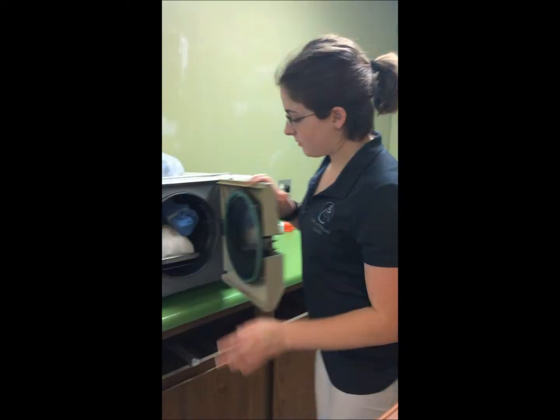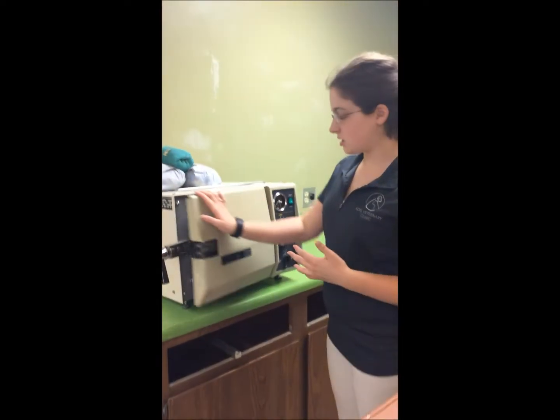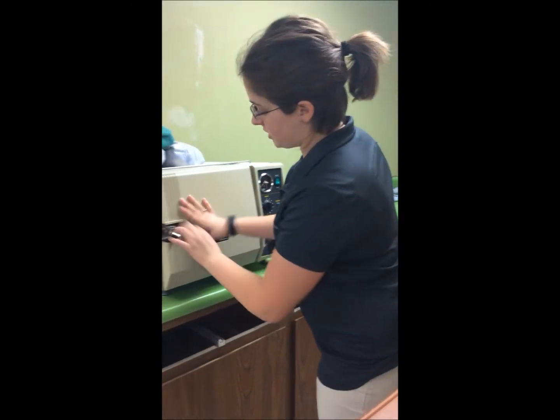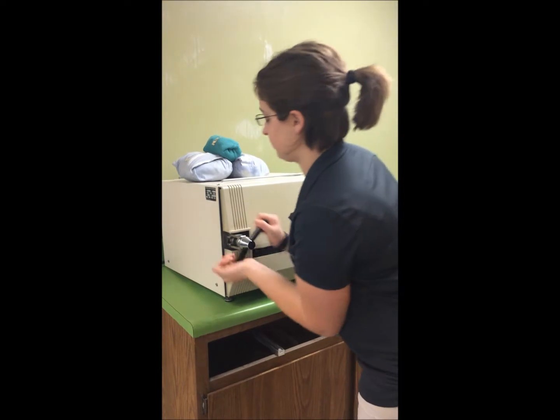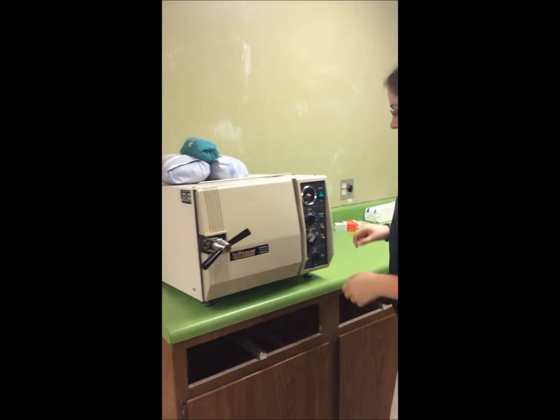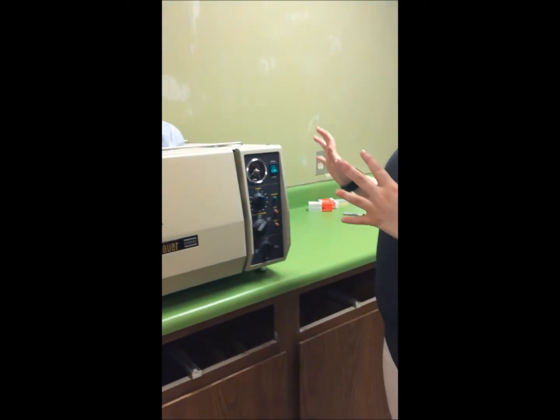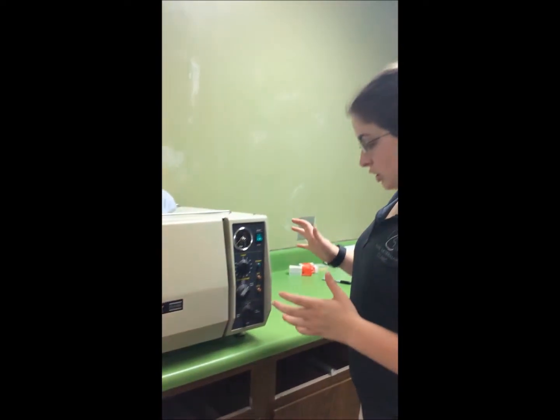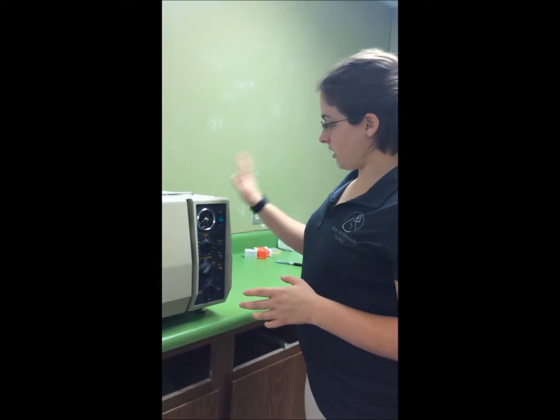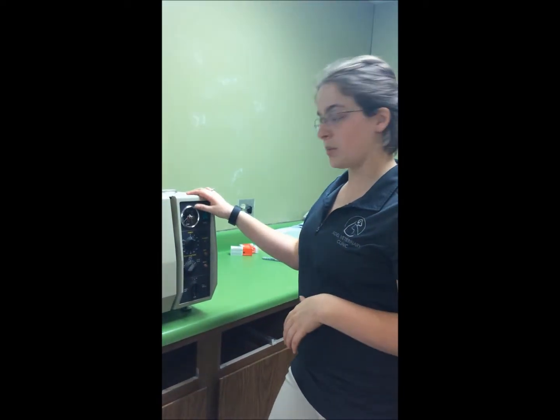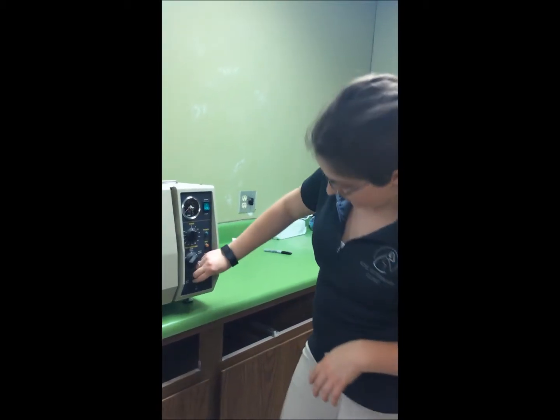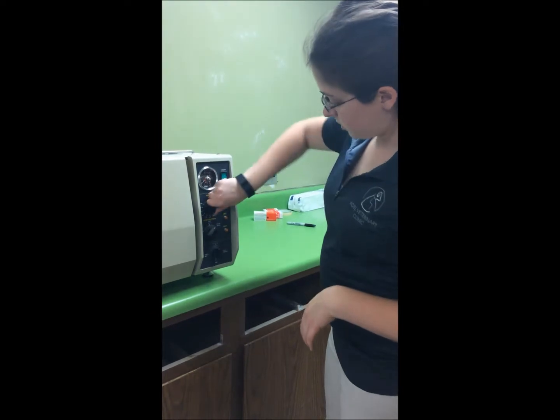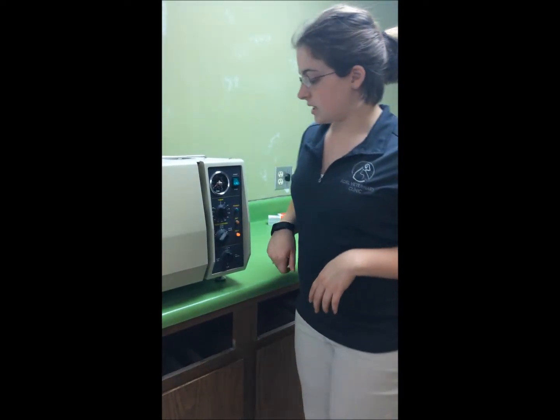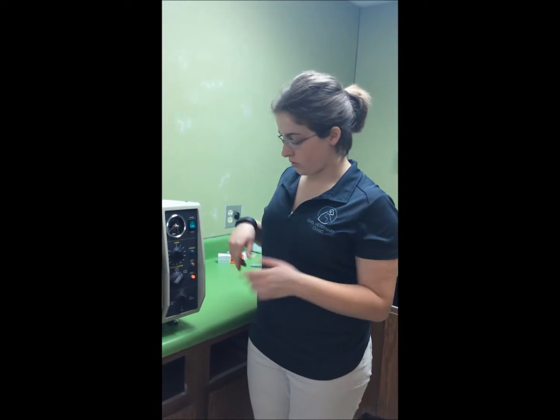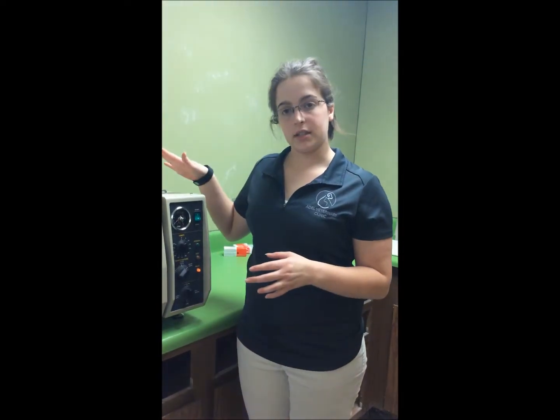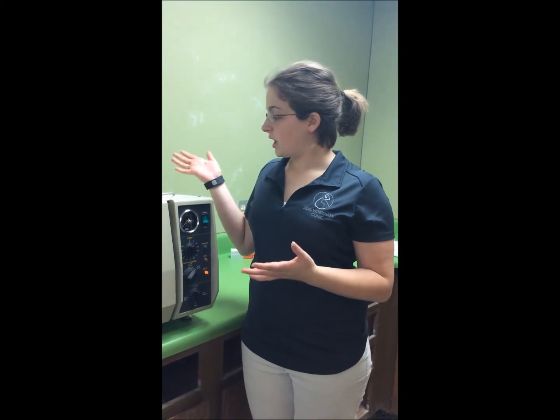Okay, so now my autoclave filled up with the water, the distilled water. So I'll go ahead and shut this and latch it. Crank it, make sure it's nice and tight. We run ours on between 250 and 270 degrees, and then we'll run it for about a half hour at 10 to 15 psi, kind of depends. And so I have it on STE, which means steam. And I will turn my timer on for 30 minutes. And in about a half hour, I will come over and put it on the dry setting and let it kind of dry itself out. And then the packs will be done.